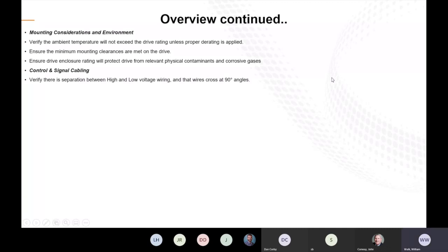For your control signal and cabling, make sure that we're using the proper type of cabling, as well as crossing your wires at 90 degrees. You also want to separate your high and low voltage wiring. There's a lot of noise being generated by these VFDs, so we want to keep those isolated. And whenever we are using analog signals or encoders, always keep that separated and use shielded cabling.